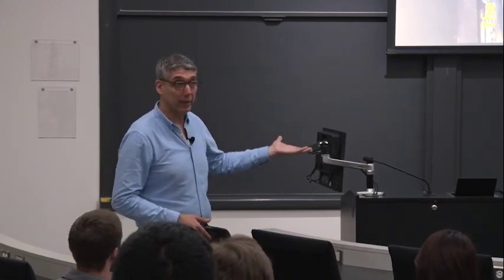At this point, trust me, it can be done, but it's very difficult, and you have to do it in a very conservative way. What you cannot do is basically not understand what you're doing and doing it all wrong under the premise that you're doing it right. This sentence here is by definition wrong. That sentence should be accompanied with a statement that says, only if you can explicitly demonstrate that under the conditions of which you are designing, self-extinction will be attained within X period of time. And that statement is nowhere to be found.